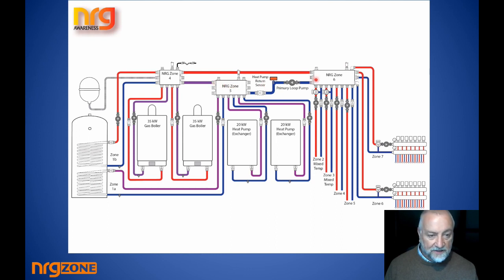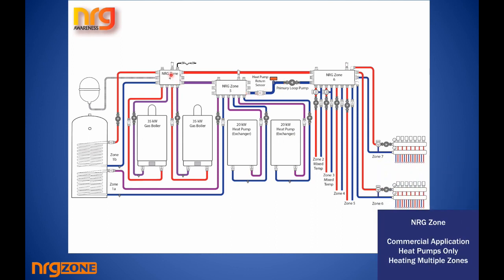At 45 degrees, it's delivered because this pump has no other choice. It can't find a circuit here to get anywhere else. It can't go through the cylinder circuit, can't go anywhere unless this pump is running. So its only choice is through this non-return valve, through to here, and it wants to get back to this pipe. So if the gas boilers were not on, the heat pumps could be just heating this zone, because it'll come to here, go through the bypass, cross here, out through that, and back around. So now the heat pumps alone can heat the heating system if that's what the system design calls for.